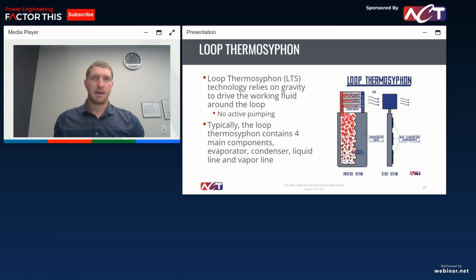So your evaporator can be many things, but oftentimes it'll be a cold plate, as you can see in the example on the right. In that left part, the inside view, depending on your application, that cold plate can be in many different orientations, or the internal geometries will change, but essentially you'll have your fluid moving through the cold plate, and it's going to be at saturation, so you're going to have a frothy, bubbly mixture, partially vapor, partially liquid, as it moves up the evaporator.